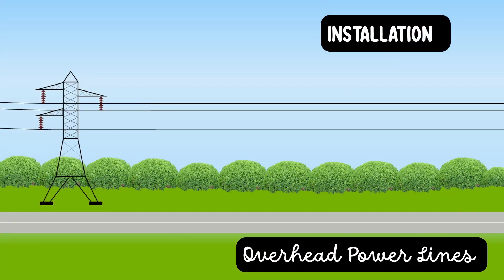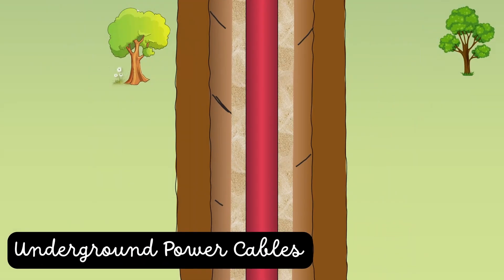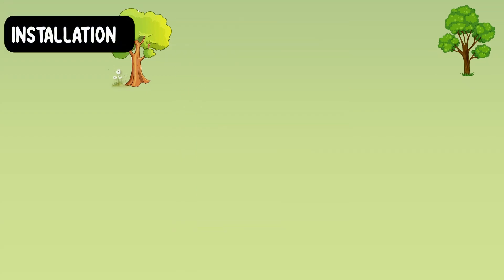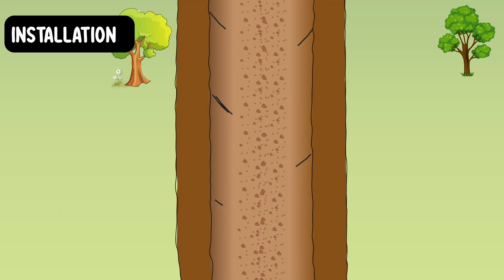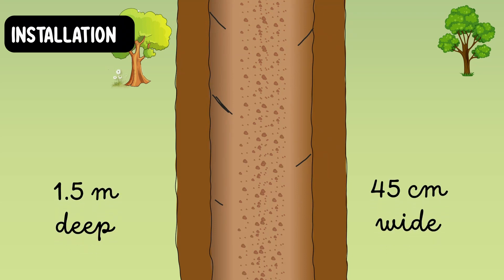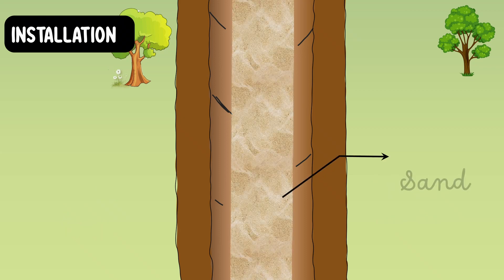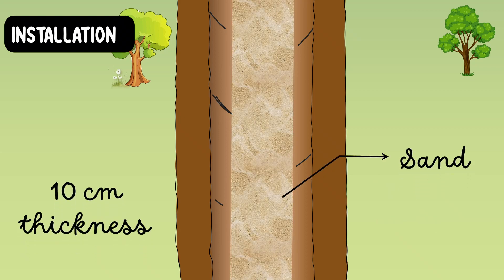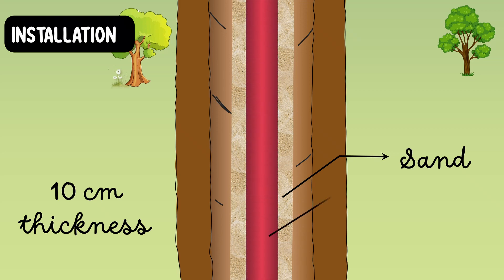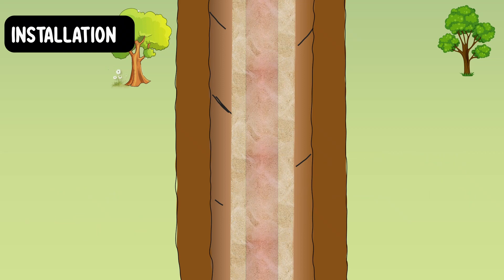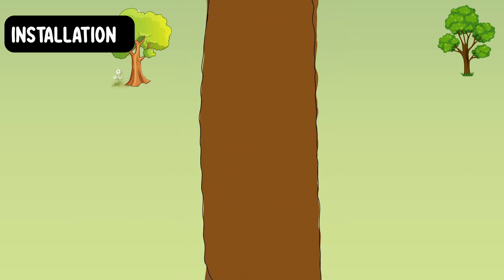The installation of overhead power lines starts with the setting of towers or poles. The power lines are tied to the towers through insulators, which give mechanical support to the power lines. The installation of underground cables requires digging a trench of about 1.5 meters deep and 45 centimeters wide. The trench is covered with a layer of fine sand of about 10 centimeters in thickness, the cable is laid over this sand bed, then covered with another layer of sand, bricks and other materials.